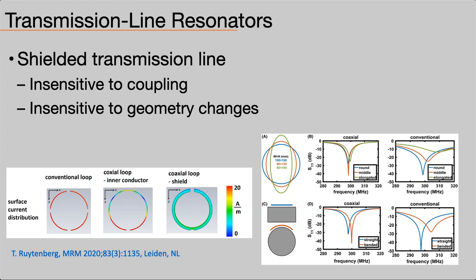If you look at the distribution of current on that coaxial shield, it's very low. Here's the conventional coil, and the distribution is pretty uniform, with very high current going on the conductor. That's a conventional loop. In a coaxial loop, you've got two loops: one is the shield, one is the inner conductor. The current concentration varies from high to low at different points on the inner loop, but the inner loop is being shielded by the outer loop, and the outer loop doesn't have a lot of current on it. So that effectively creates this effective high impedance.